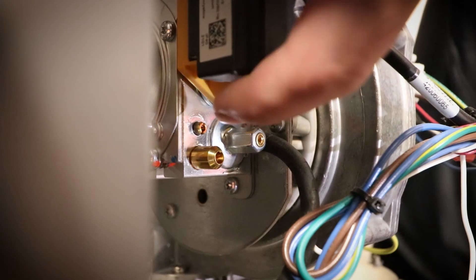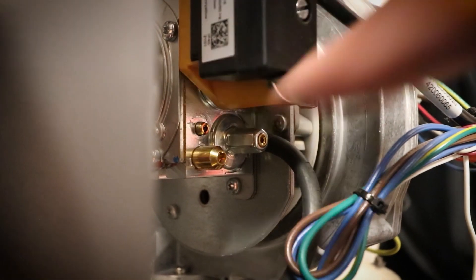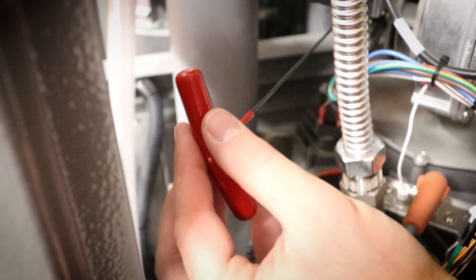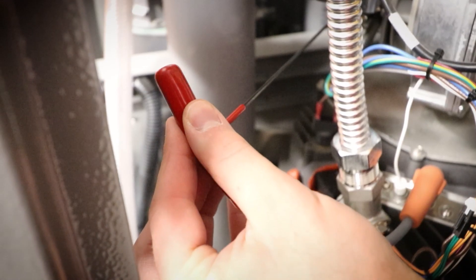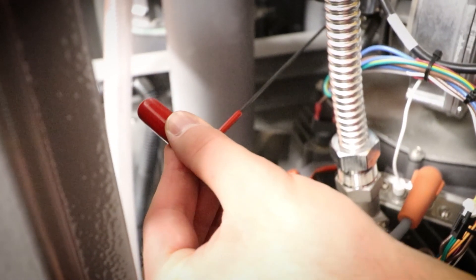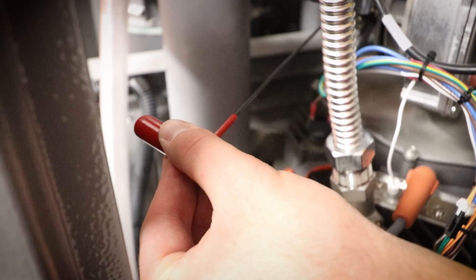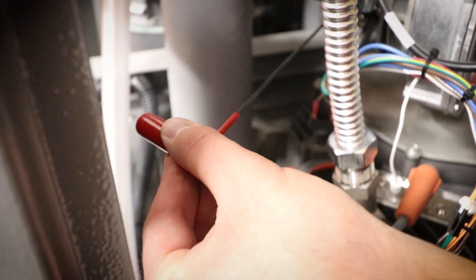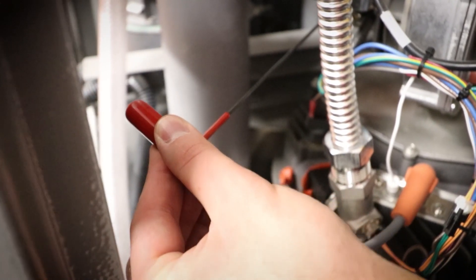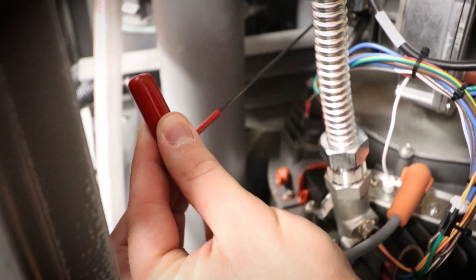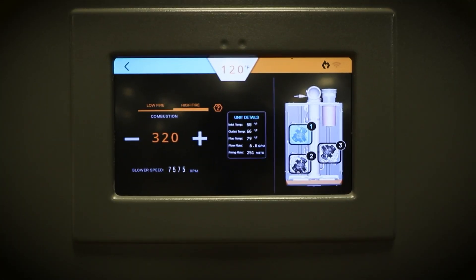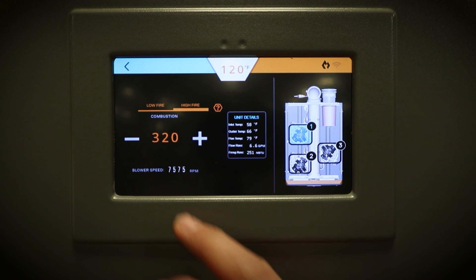If an adjustment is needed, locate the high fire screw on the gas valve and turn it counterclockwise to increase the CO2 percentage and clockwise to decrease the CO2 percentage. Do not adjust more than one quarter turn at a time. When the CO2 and CO values have settled in the acceptable range for at least two minutes, you can enter low fire by pressing low fire on the display screen.